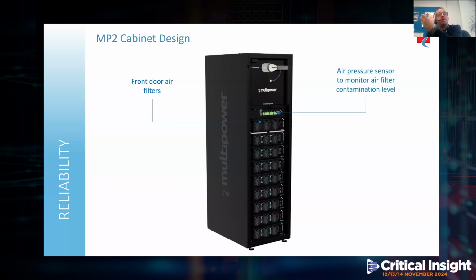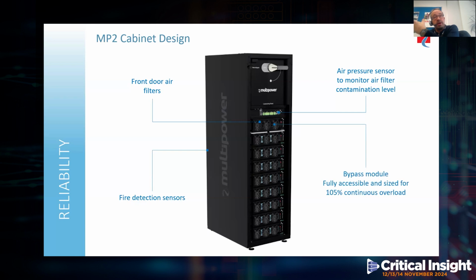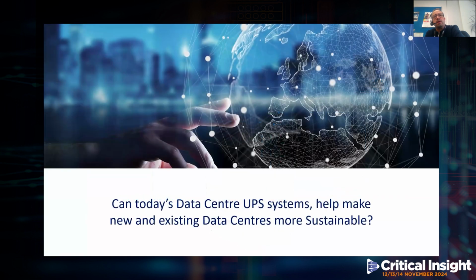Each cabinet is fitted with air pressure sensors so that we can monitor the contamination levels of the air filters which are fitted to the doors. The rear of the cabinets are fitted with fire detection sensors adjacent to the main connection assemblies. And the static bypass module, which is critical to the system, is fully accessible and sized for 105% continuous overload.